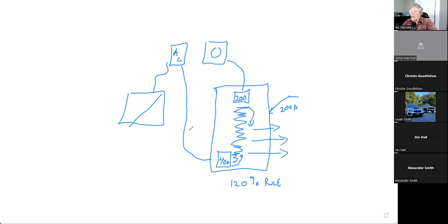Well, then what size wire would I use and what size array? Well, I could figure this out. We know that the power coming from the utility is 240 volts AC. Well, then the power coming from the inverter has to be 240 volts AC, right? It's got to match exactly what's out there on the grid. All right, so if it's 240 volts and 40 amps, it would be very tempting to just say, all right, 240 volts times 40 amps.